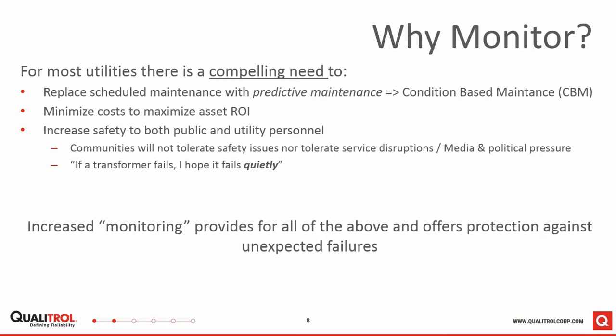Also, we need to consider the safety aspect of voltage transformers. As we'll see on some later slides, voltage transformers can and do fail. They fail in urban areas, and this can create a risk to the public. And monitoring will help to mitigate that risk by informing the user of an emerging risk.